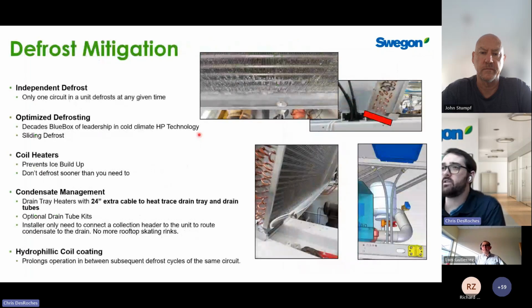So it's really important to have a plan and a strategy to be able to deal with that condensate. Feedback from a lot of architects and mechanical engineers is that roof membranes don't really like having ice. Water freezing and melting on the roof throughout the winter can cause damage to the membranes. And Blue Box, we have a lot of experience in cold climates. We're market leaders in Scandinavia and Northern Europe, so we have a lot of experience with cold climates and optimizing our defrost. So part of that is having dedicated logic on the machines. That was a requirement for the launch in North America to be able to do independent defrosting on these large machines to mitigate the effects of water temperature. But we also have a lot of tricks figured out with defrosting. So for example, we don't just shut the fans off during defrost. We actually modulate the speed of them according to the head pressure, because through our experience, we figured out that that's the most effective way to melt the ice and have short defrost cycles. We also have basically a way to tune the defrost according to the local conditions in the field through the parameters.